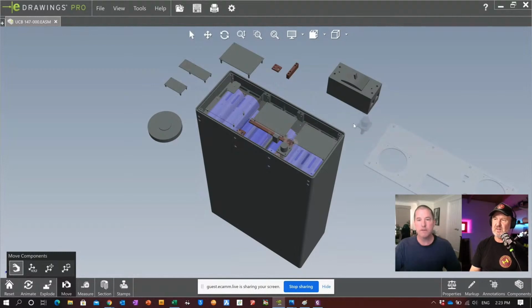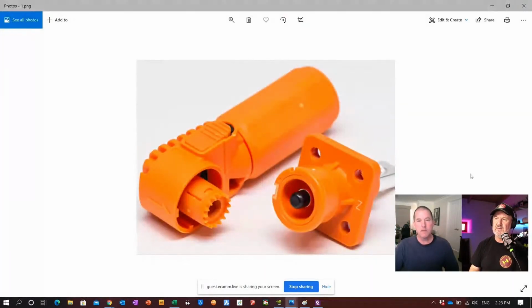Now I note before we went on air, I was asking about those connectors, and they looked a lot like Amphenol connectors because previously you used solid copper bar. Why the change? That's right - because we're into the sort of unsafe voltage range at 147 volts nominal, we're using these touch-free connectors here, which are rated to 350 amps.